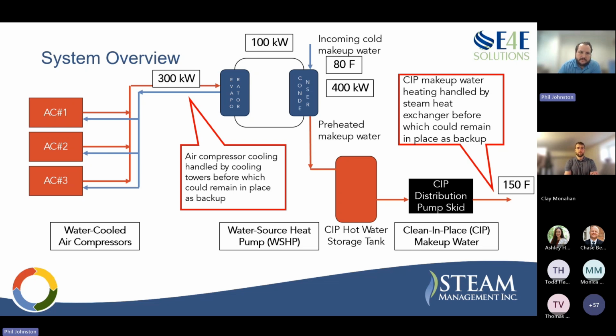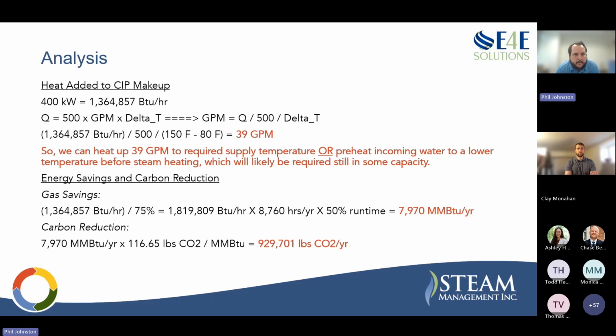So as far as the value of that, we're now preheating that water to 150 degrees. You could say that maybe this water's final temperature needs to be 160 or something like that. And if you do the simple math, that comes out to 39 GPM. So as far as our options here, if the flow of makeup water is less than 39 GPM, then we would be able to heat it all up to 150 degrees. And then the final 10 degrees would have to be covered by the steam. Or if the flow is much higher than that, that temperature would come down. So instead of 150 degrees, maybe we just preheat to 120.